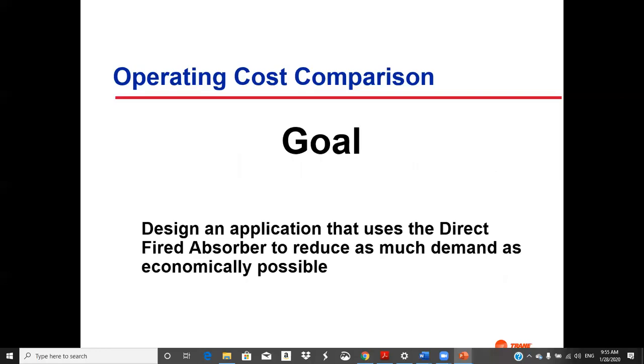Okay, so the goal in this presentation, which is a little bit of marketing material by Trane, I guess, shows one way that you can make this stuff pay off. Design an application that uses the direct fired absorber to reduce as much demand as economically possible. That demand charge in your electric bill: you get billed on the electrical energy, kWh, that you use, but you also get billed on that peak, kW. And if you're running a big chiller like that, say that centrifugal is 0.6 kW per ton, 1,000 tons is 600 kW, you could be paying $20, $25 a kW per month if you run that during the on-peak period.